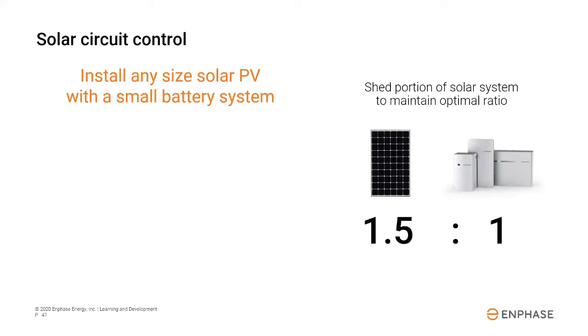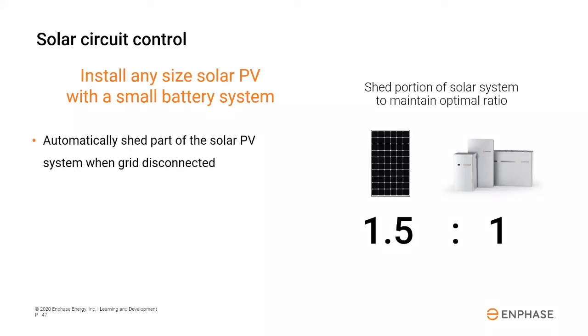Now, the advantage of solar circuit control is that you can go above this ratio because you can effectively use load control to turn off part of the solar array. So you could have a much larger PV system, and when the system goes into backup power mode, becomes disconnected from the grid, you can shed part of the PV system so that you maintain this ratio. So you only have this 1.5 to 1 ratio after the system is disconnected from the grid.